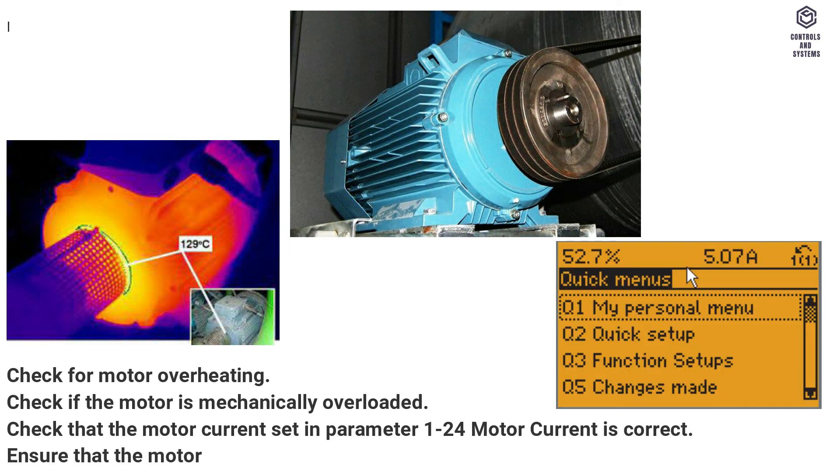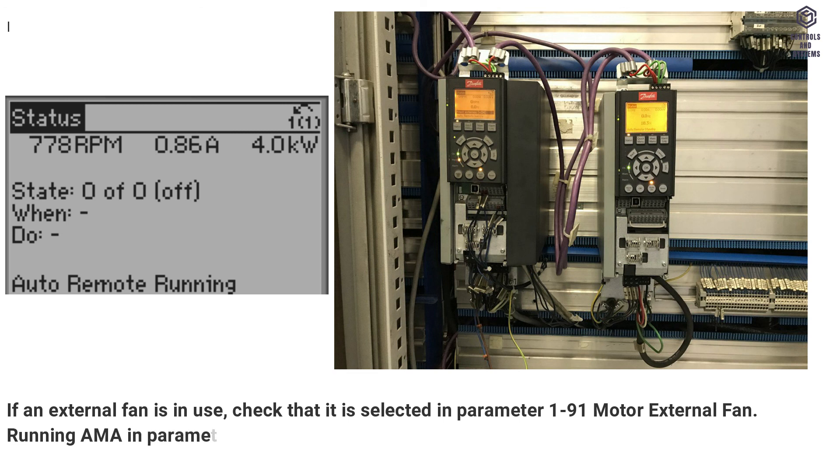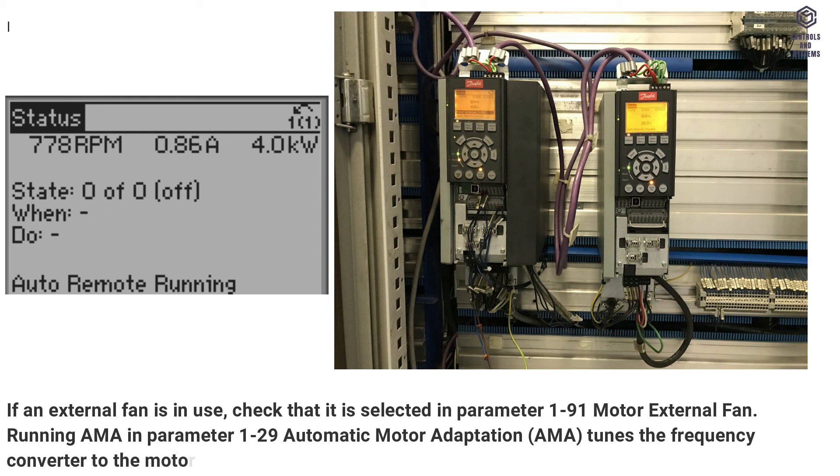Ensure that the motor data in parameters 120 to 125 is set correctly. If an external fan is in use, check that it is selected in parameter 191 motor external fan. Running AMA in parameter 129 automatic motor adaptation, AMA, tunes the frequency converter to the motor more accurately and reduces thermal loading.